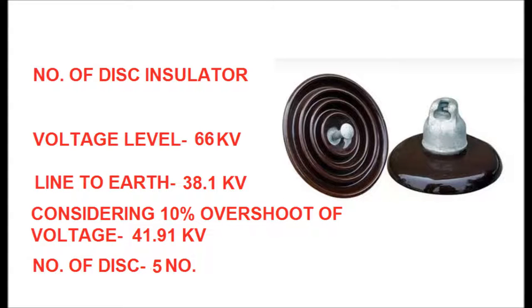For the 66 kV voltage level, the phase-to-phase voltage is 66 kV. The line-to-earth voltage is 66 divided by √3, equal to 38.1 kV. Considering 10% overvoltage: 38.1 × 1.1 = 41.91 kV. Dividing 41.91 by 11 gives approximately 4. Taking an additional margin of 1, the suspension type string uses 5 discs and the tension type string uses 6 discs for a 66 kV system.